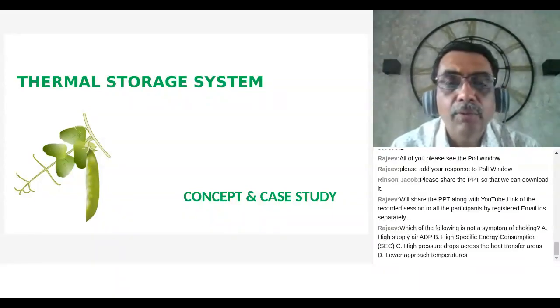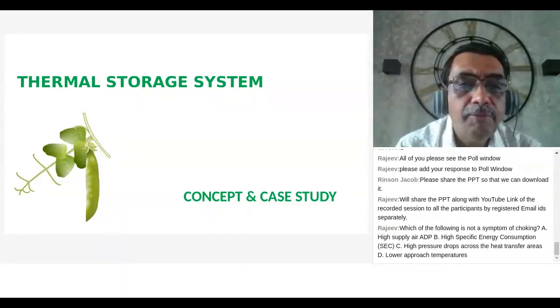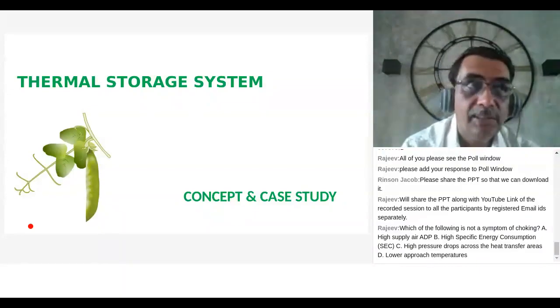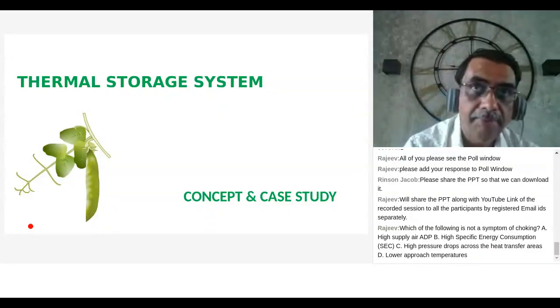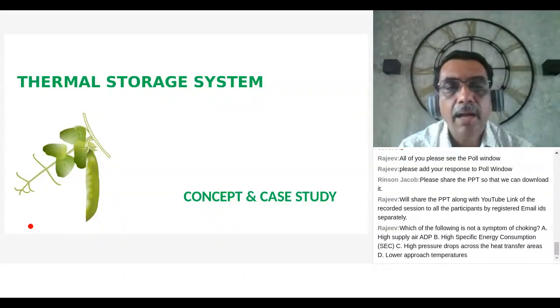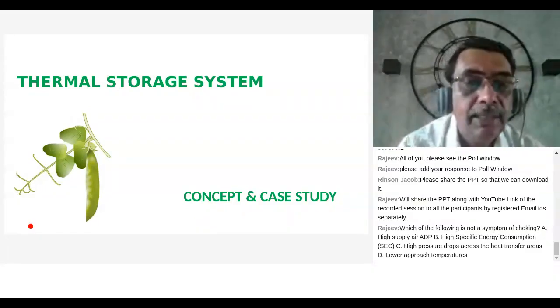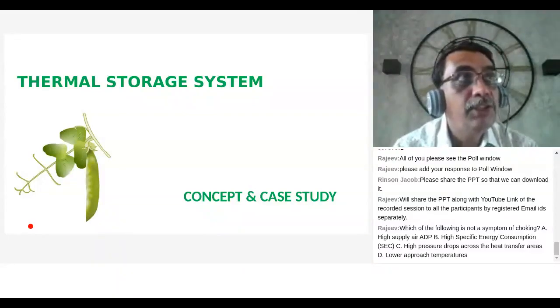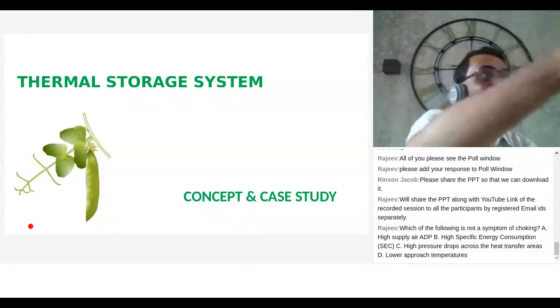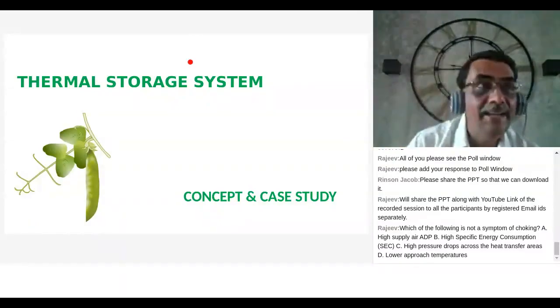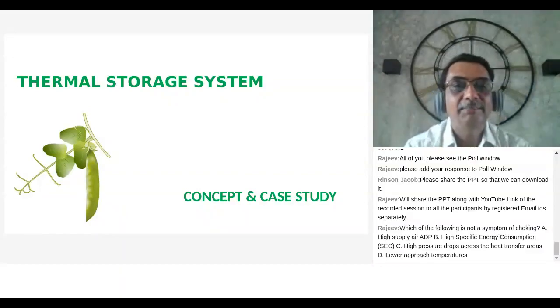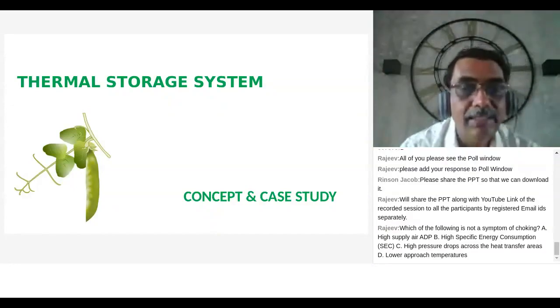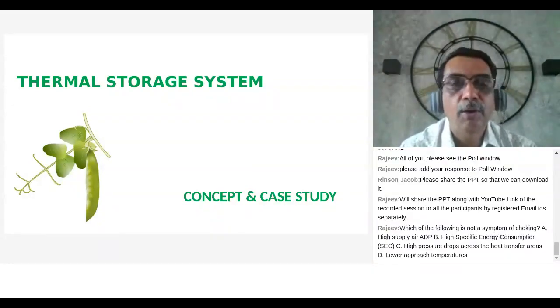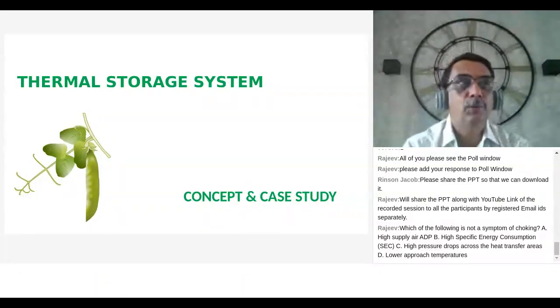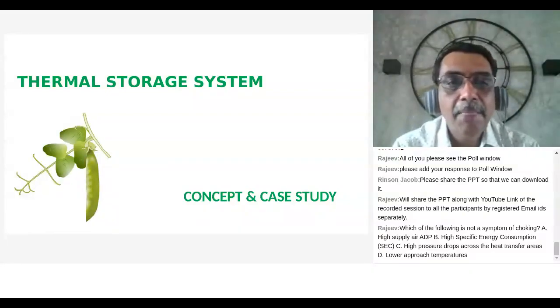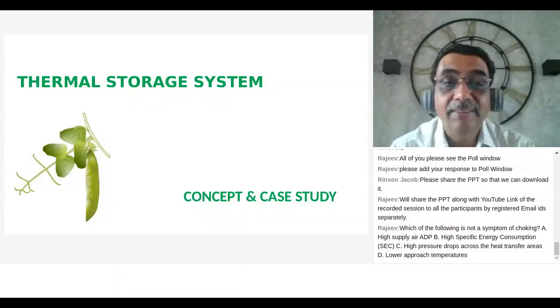So guys, quick, not even half a minute to respond. Which of the following is not a symptom of choking? I am asking a question which is not, means others are. High supply air ADP, high specific energy consumption, high pressure drop across the heat transfer areas, or lower approach temperatures. Which is not a symptom of choking? First one is high supply air ADP. Second is high specific energy consumption. Third is high pressure drop across the heat transfer areas. Fourth is lower approach. Which of the four is not a symptom of choking? Give your poll, which means the other three are symptoms of choking.